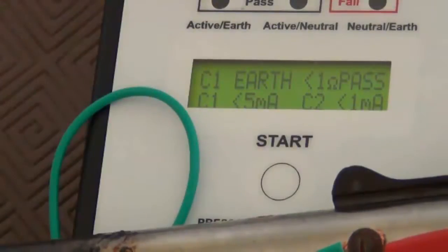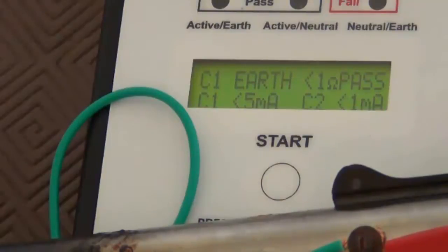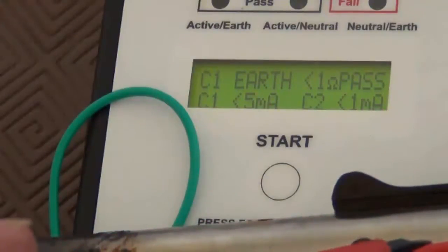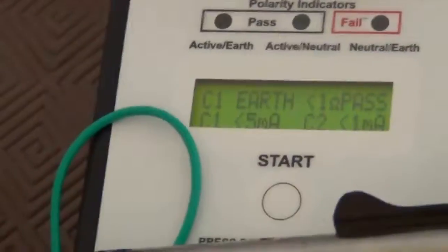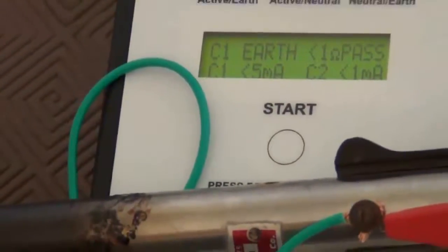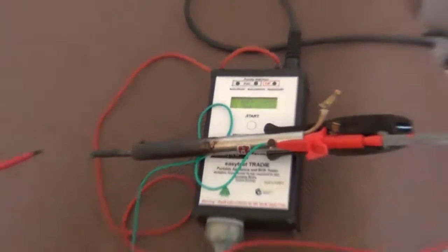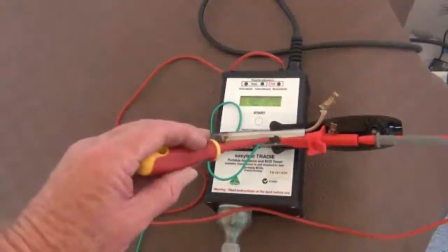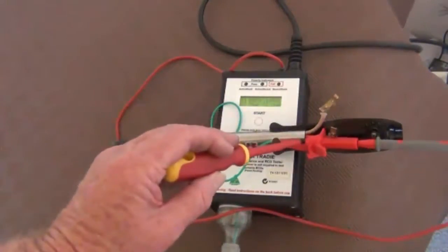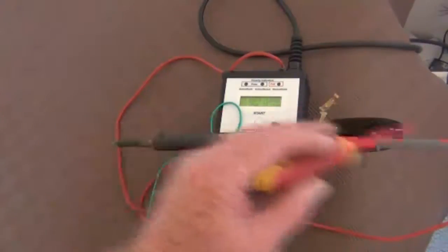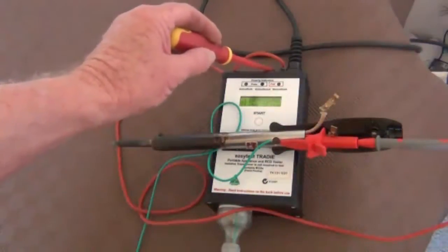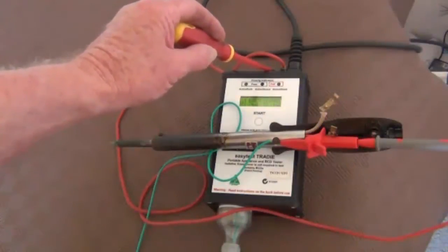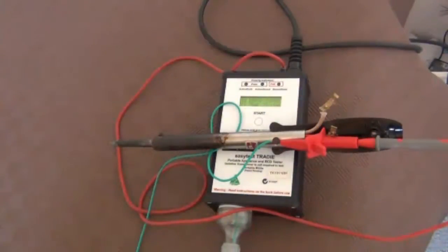Okay, you'll notice that the earth wire is connected directly to the unit, to the normal earth pin, to there. The probe is connected. That gives me a return path. I'll just zoom out again. And there you can see the earth connected to the unit, to the earth screw, to the probe connected to the exposed metal, and returned back to the probe connection on the tradie. This is the earth resistance test.